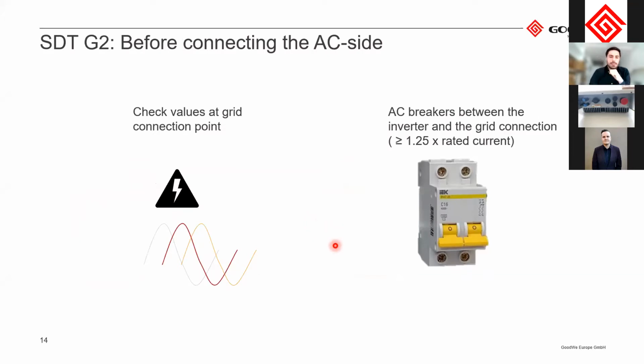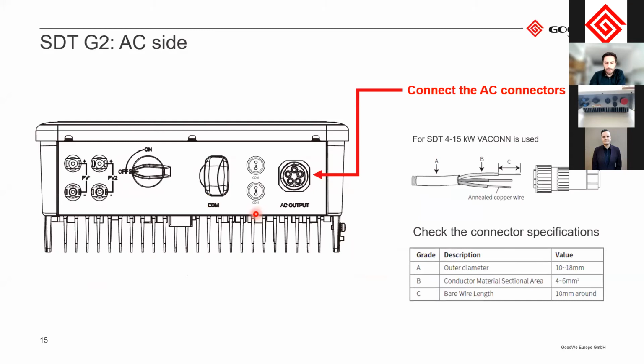And before connecting to the AC side, please check the values at the grid connection point. Please measure the voltage and the current to check that it's correct and you know which phase is which. After that, we also do recommend that you install proper AC breakers. So in case something happens, you can turn off the AC output. So firstly, you can start with connecting the AC side. So then you basically just use the proper wires. Please check the manual again that you have the correct wires. And then you connect the 3 lines as well as the neutral and the ground, and connect it to the AC output.